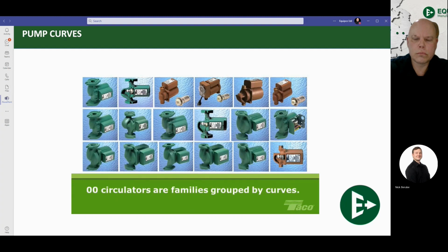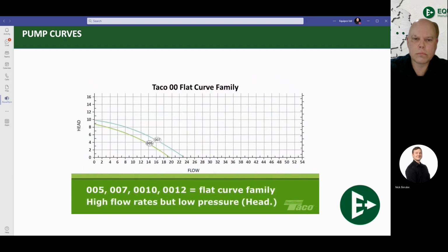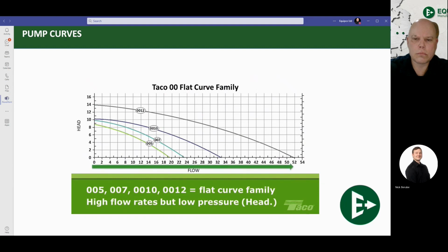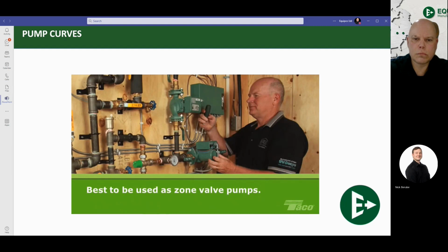It's helpful to think of Taco fixed speed circulators in terms of families that are grouped together by their curves. The 005, 007, 0010, and 0012 circulators are all members of the flat curve family. As you can see by their curves, they can produce high flow rates but relatively low pressure. A smaller flat curve pump, such as the 005 or 007, is ideal as a system circulator for zone valves in standard residential jobs or as a zone pump. The larger flat curve pumps, like the 0010 and 0012, are designed for larger residential jobs or light commercial applications.